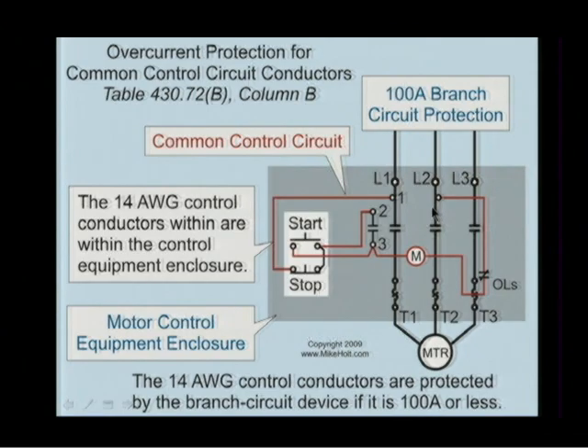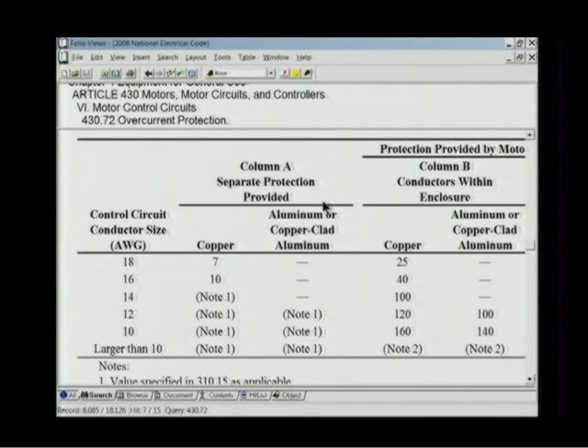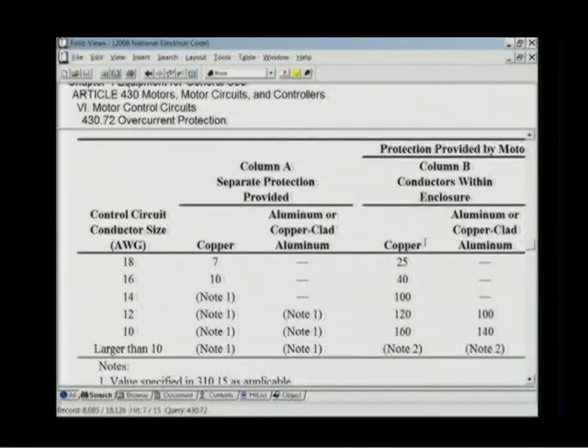Let's take a look at our graphic. Because of the shading, Mike has made it real clear that the control conductors are contained within that particular enclosure. So column B says protection is provided by the motor branch circuit. Column B, conductors within the enclosure. And what size wires do you run, Eric? Well, if they're within the enclosure, control wiring is sized by the manufacturer. I'm glad you said that. If they're within the enclosure, the start-stop button is part of the controller assembly, so column B applies, but since it's part of the enclosure, column B doesn't apply to us in the field because it's automatically done by the manufacturer. Can I cross out column B? Everybody accept that? All right.